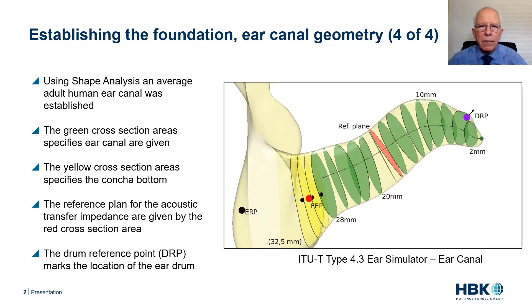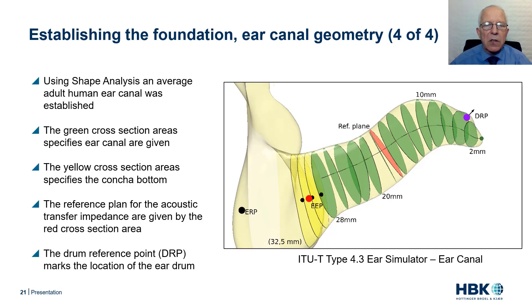A complete description of the ear canal geometry has been accomplished in a large table that can be used by relevant standards organizations like the International Telecommunication Union Telecommunication Sector, or ITU-T. The ear canal and method illustrated on the slide have been adopted by ITU-T and can be found in ITU-T P.57 standard, and has become the ear canal of a new ear simulator named the Type 4.3 ear simulator.